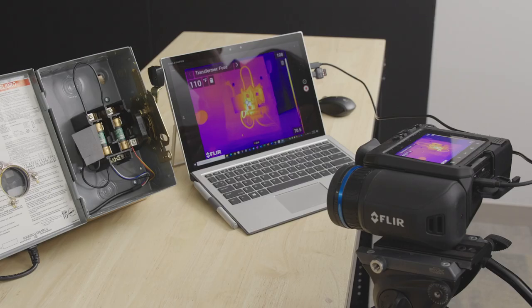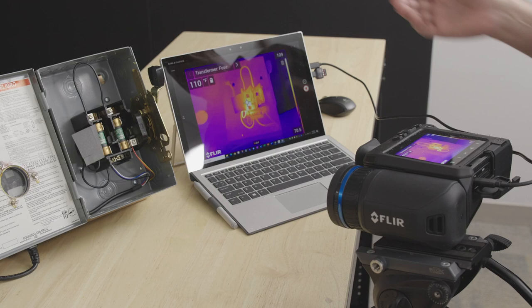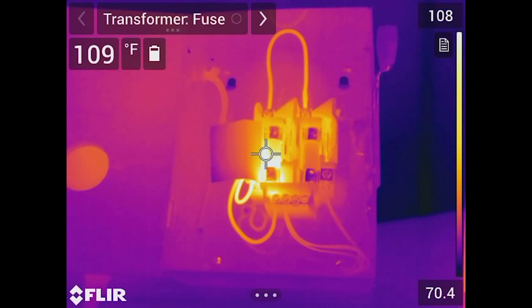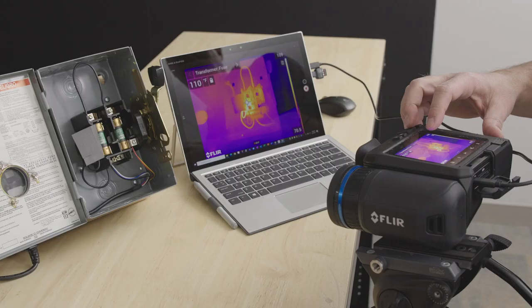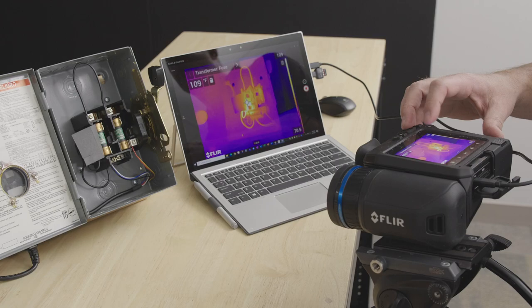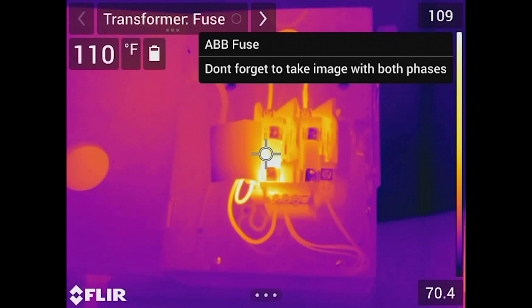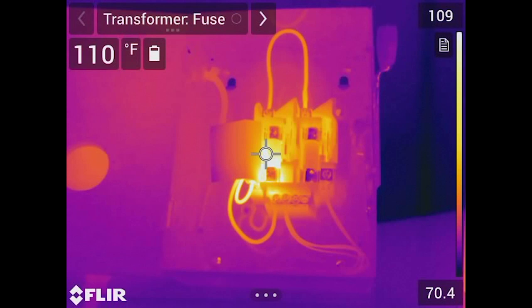We've transferred the route from the computer onto the SD card. Now the thermographer goes out in the field, and when you boot up the camera it's already prompting you: the first inspection point is the fuse on the transformer.